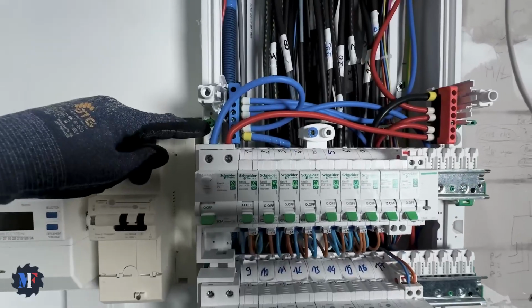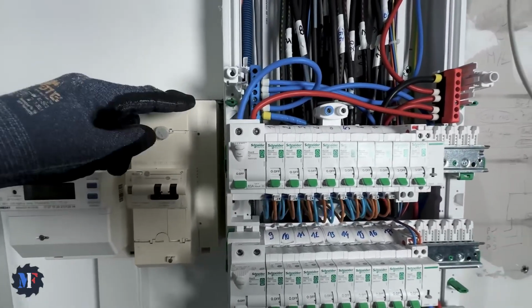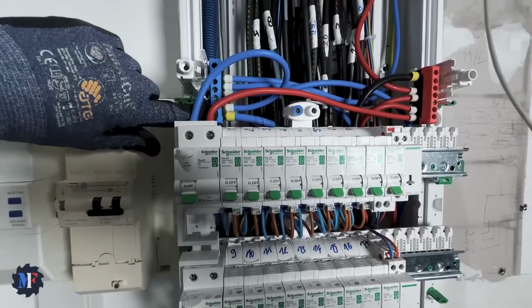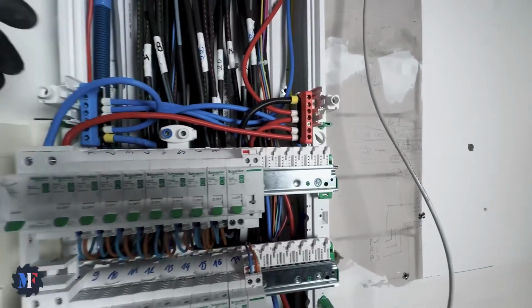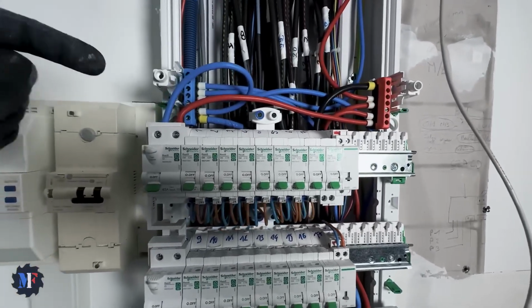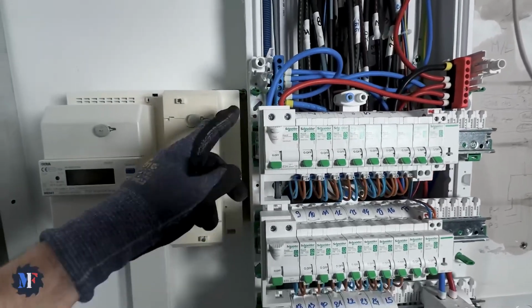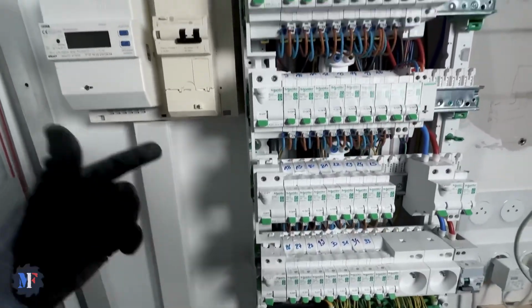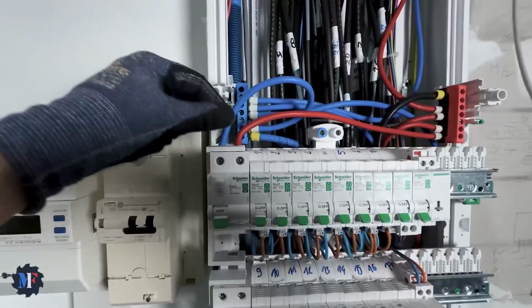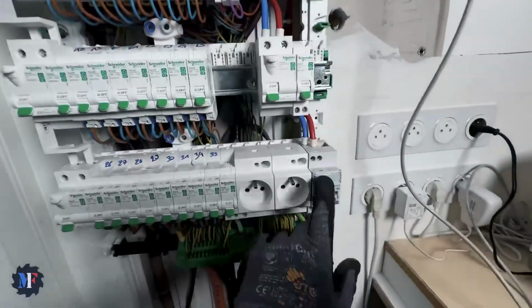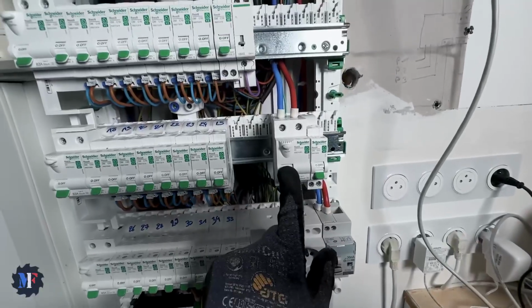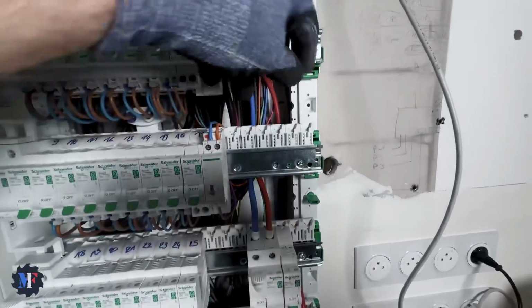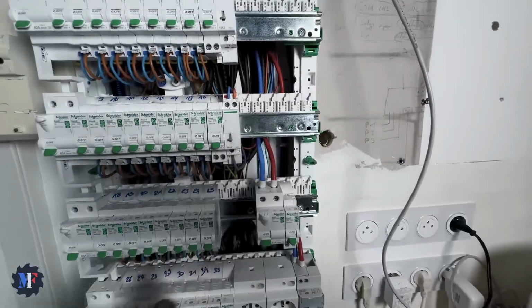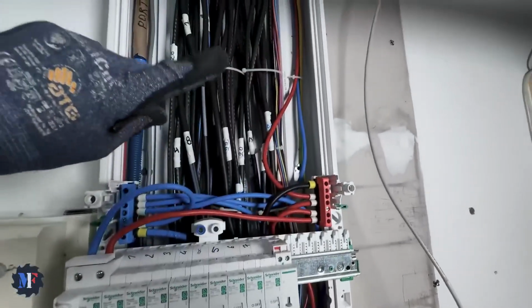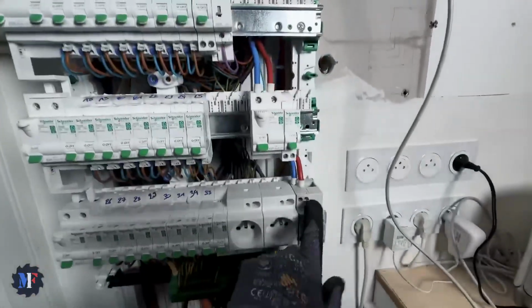The main power supply comes out of the main circuit breaker in 25 mm2 with the yellow cable end on the neutral and the phase. So the terminal blocks are powered, and I can now power my residual current devices with the vertical bus bars to supply each switch. So with 16 mm2 on the neutral and phase, and the same for the charging station and this residual current device. On a 5 module rail, I added another one above it in case I need to add another residual current device. I also have my secondary panel upstairs, which gives me 1, 2, 3.